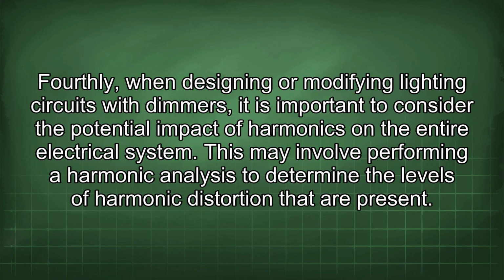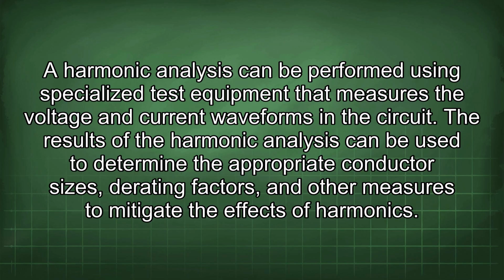Fourthly, when designing or modifying lighting circuits with dimmers, it is important to consider the potential impact of harmonics on the entire electrical system. This may involve performing a harmonic analysis to determine the levels of harmonic distortion that are present. A harmonic analysis can be performed using specialized test equipment that measures the voltage and current waveforms in the circuit. The results of the harmonic analysis can be used to determine the appropriate conductor sizes, derating factors, and other measures to mitigate the effects of harmonics.